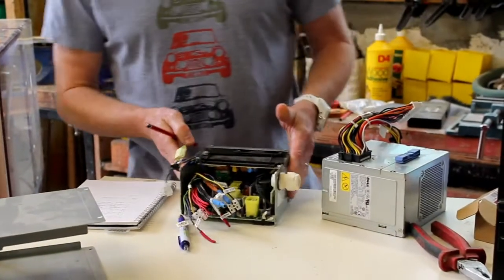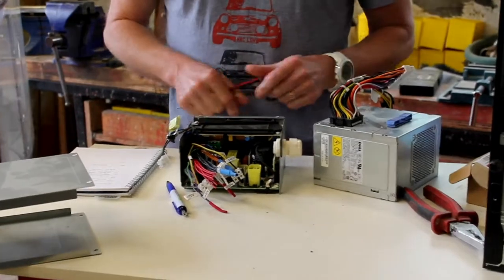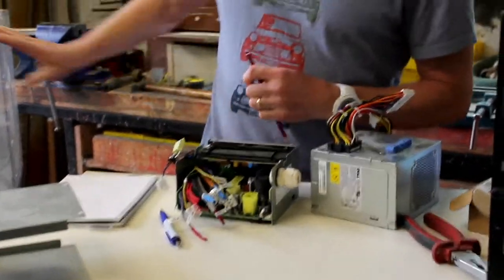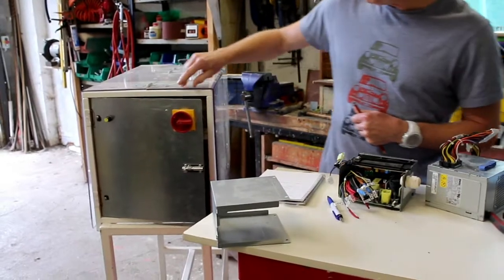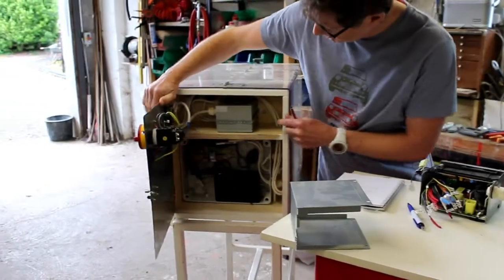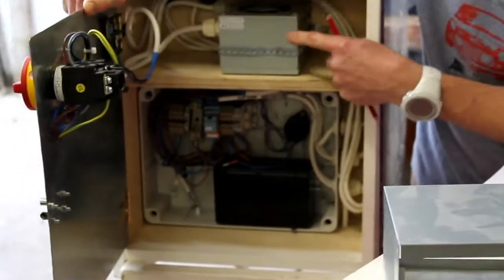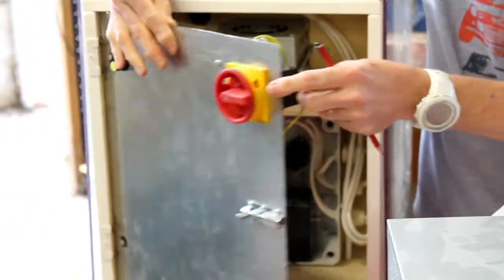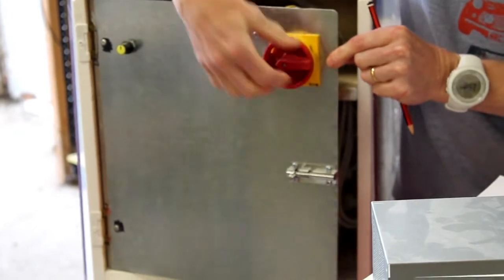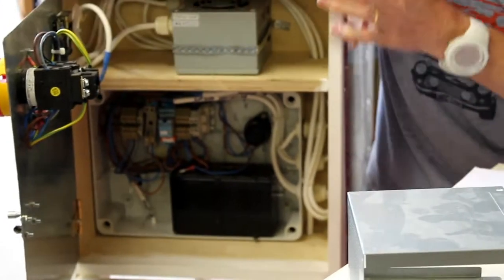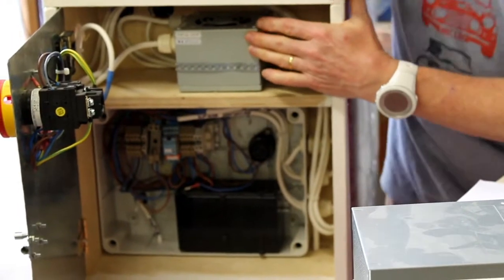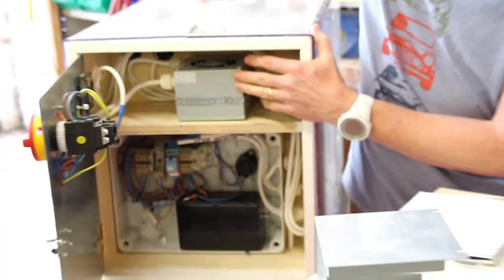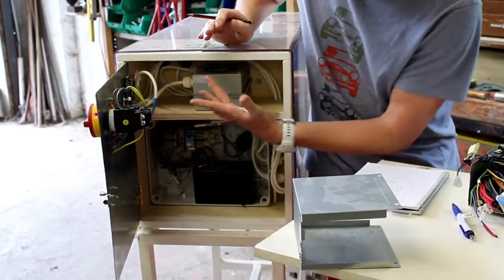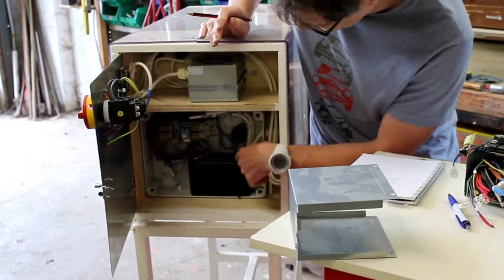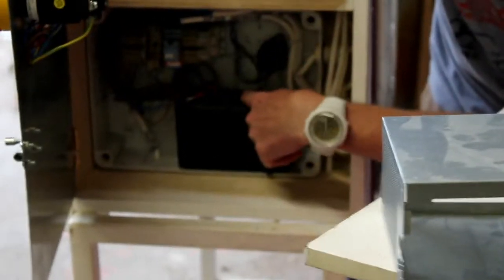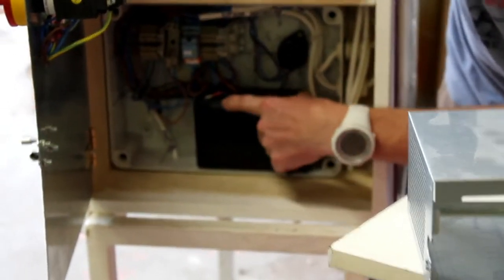So on to the use of it in the ventilator. This is the ventilator here. We have the power supply located here. The power supply is switched on via the main isolator here, and we're using 12 volts to supply the motor for driving the ambu bag, and we're using around 14.5 volts that comes out of this one to charge the battery down here. This is the control cabinet here, which controls the motor, the charging of the battery, etc.